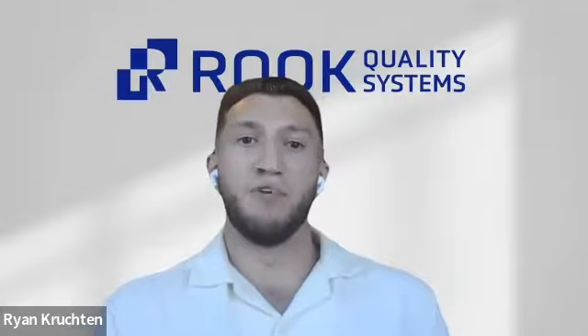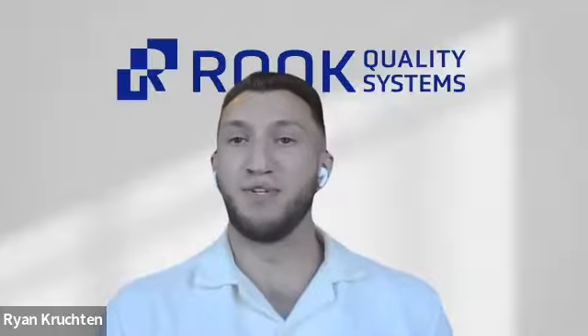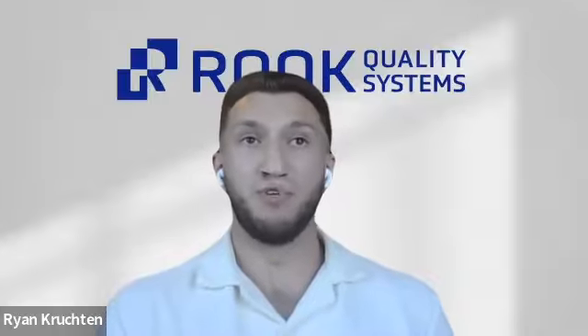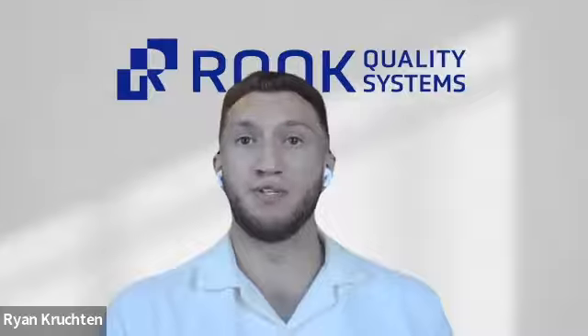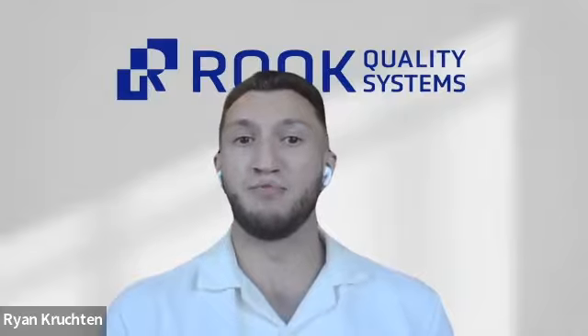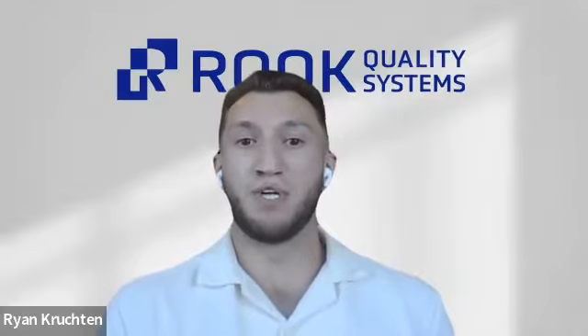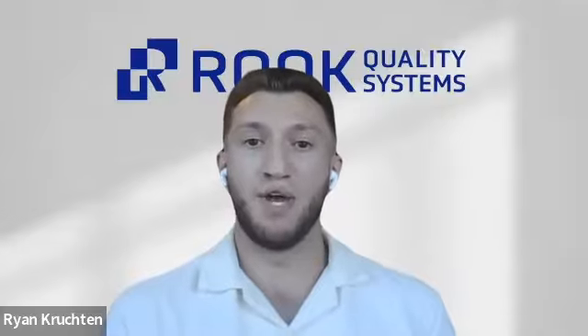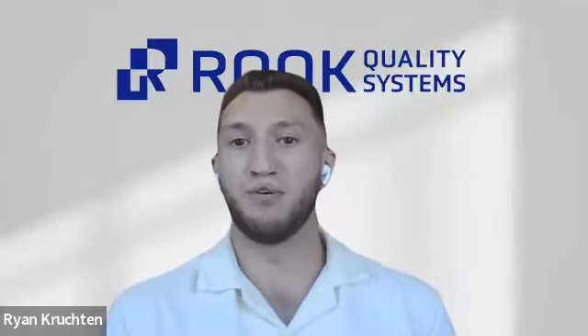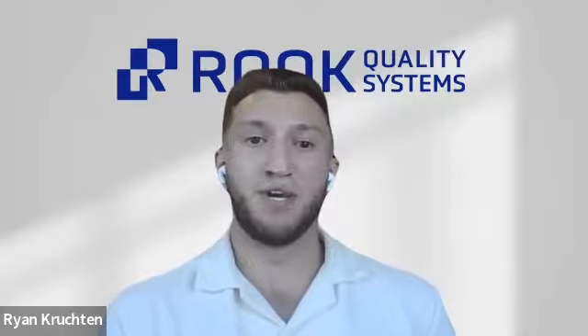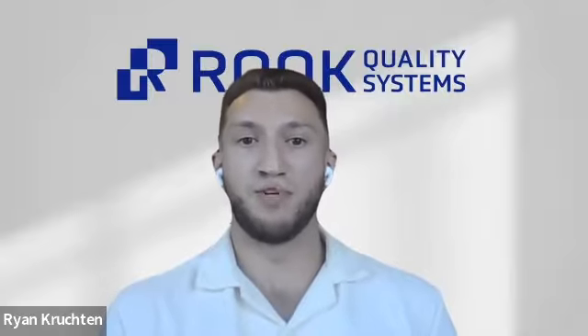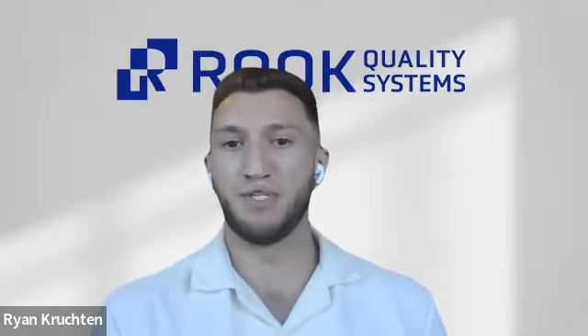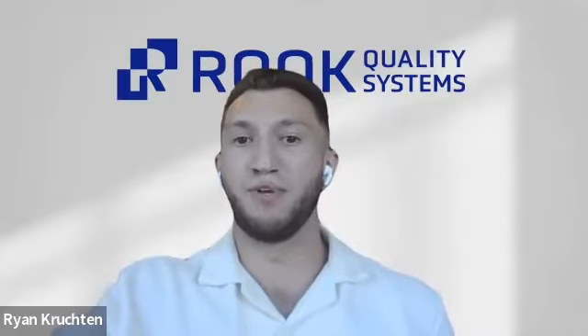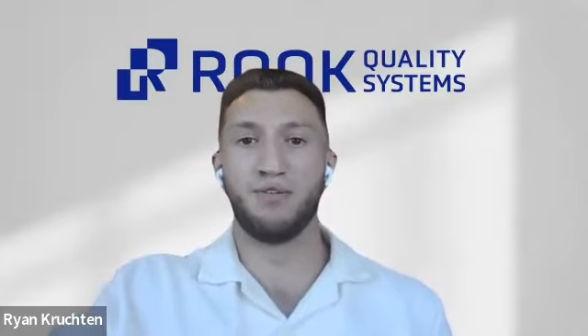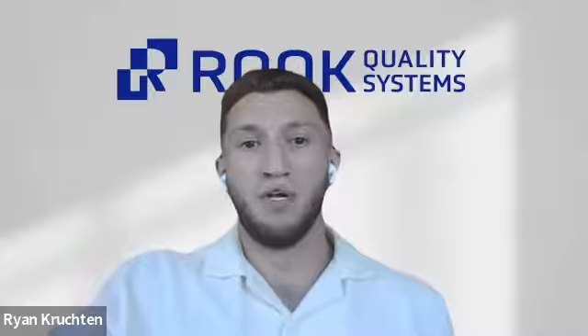So similar to AI and ML, it's hard to talk about software without considering cybersecurity. And the good machine learning practices guidance starts to get into some of those questions. This was a collaboration between the FDA, Health Canada, and the UK's MHRA. It emphasizes 10 guiding principles for trustworthy machine learning-based medical devices and starts the conversation on integrating cybersecurity risk management into the development process.